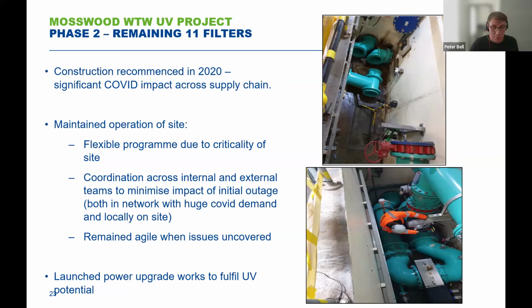The next challenge was around managing how we got in and done this work. So we had a 24-hour window to get the critical pipework installed, which is this top pipework that you can see in the top right-hand corner. That's the backwash main, what you can see there. As I mentioned earlier, when we done filter 9, getting into filter 11 not washing filter 11 was a fairly straightforward task because we could stagger the filter washes to do that. But when we started to get down into the lower numbers, like the 1s and 2s, the way that the ring main affected things was that when we broke into that pipework and made those isolations, we weren't able to wash the upstream filters on that specific leg because the water wasn't able to flow there, and we didn't want to go the long way around.